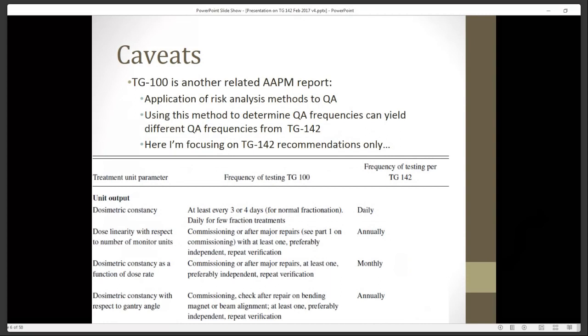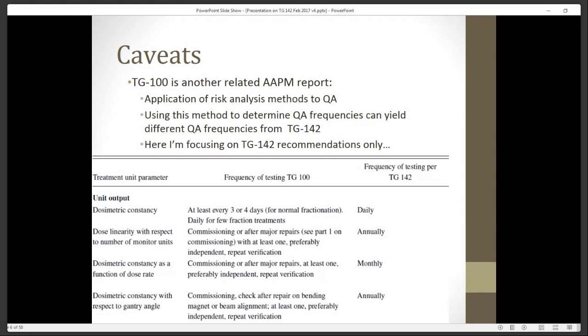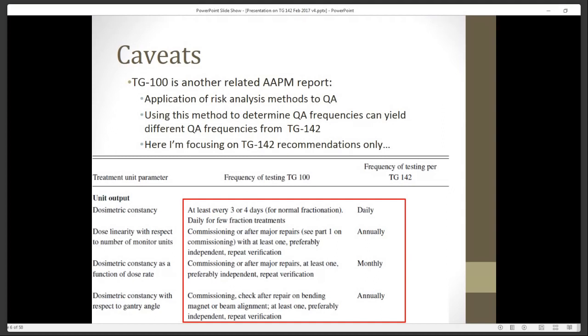Another report to be aware of is Task Group 100. This is somewhat related because they also go over QA and methods of developing QA, risks, tests, and tolerances. TG100 is really an application of risk analysis methods to QA. That method isn't necessarily going to give the same results as the recommendations from TG142, as shown in a table from TG100 where risk-based analysis can give different frequencies for certain tests. In this presentation, we're focusing on TG142 and not going to look further at TG100.